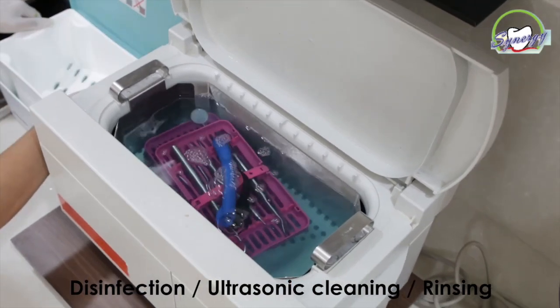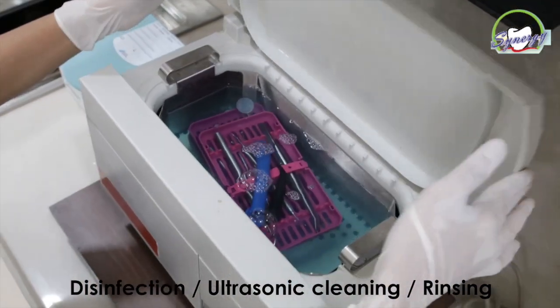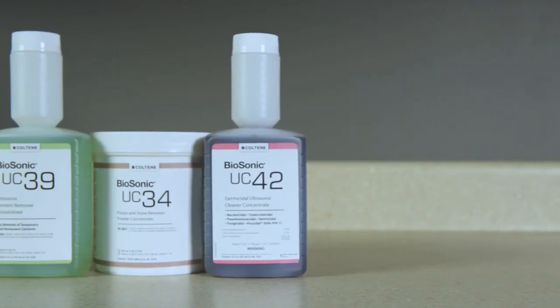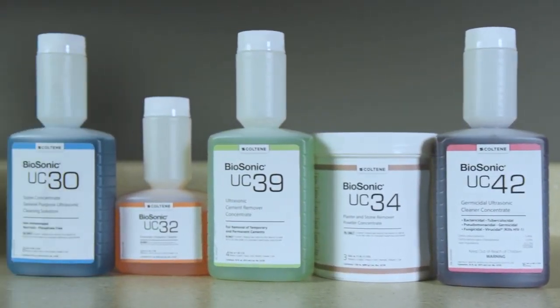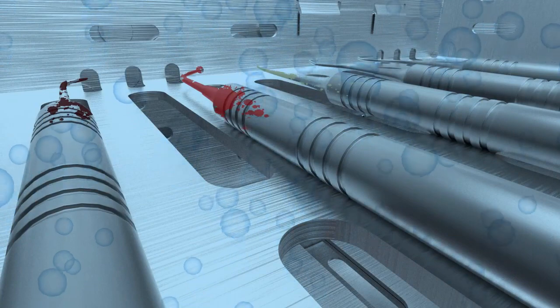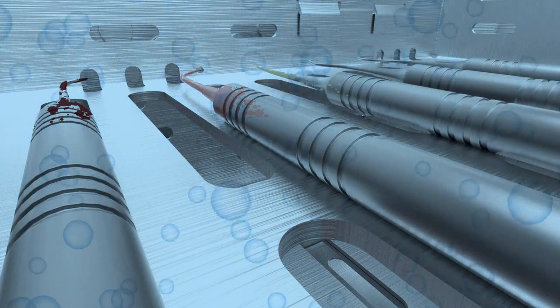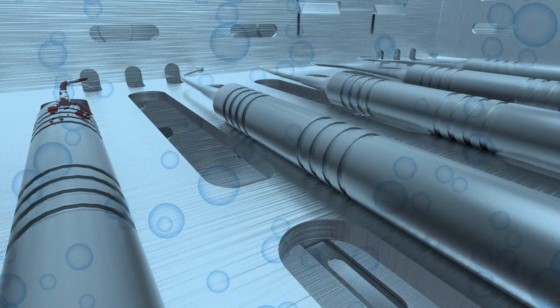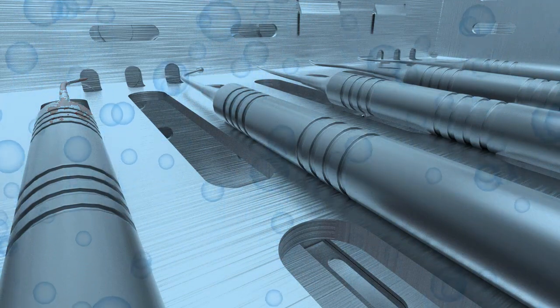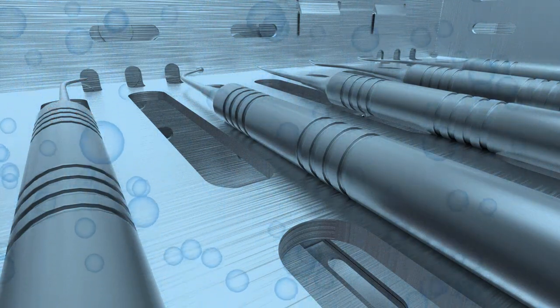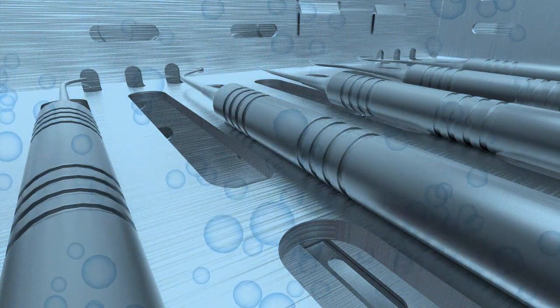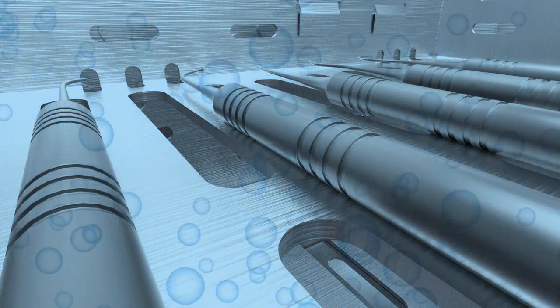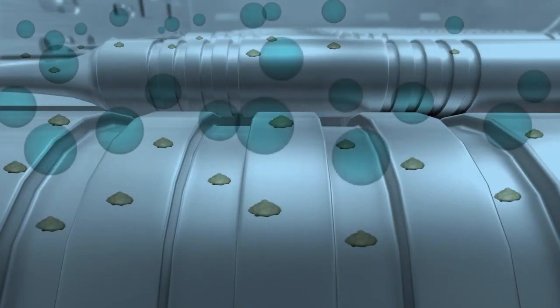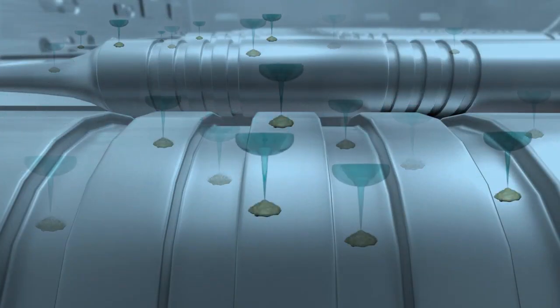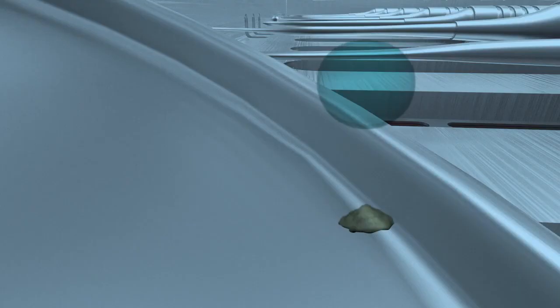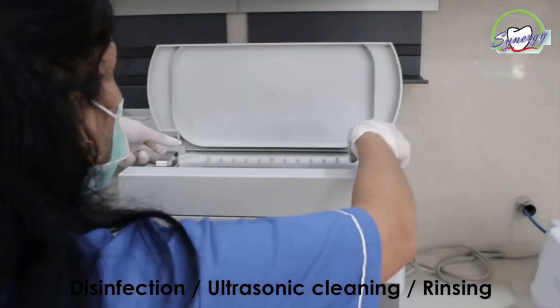The sound waves are enhanced by specially formulated cleaning solutions which create high-energy cavitation. During cavitation, millions of bubbles form and implode or collapse. This releases an enormous amount of energy and shock waves which scour the surface of the instruments. This powerful scouring reaches into minute crevices, removing large and microscopic debris which manual brushing cannot reach.